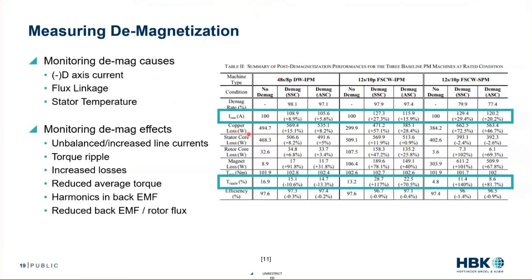You can monitor copper losses, but that's calculated — you increase measurement uncertainty. Current directly is a direct measurement. That's a really easy measurement to make over time and start to look at: is this creeping up, even for a very small amount of demagnetization?